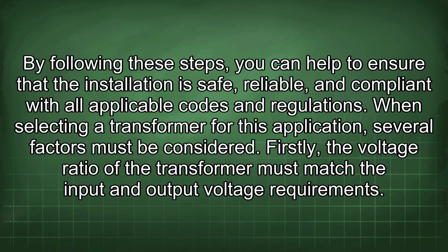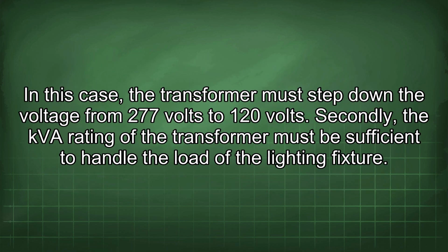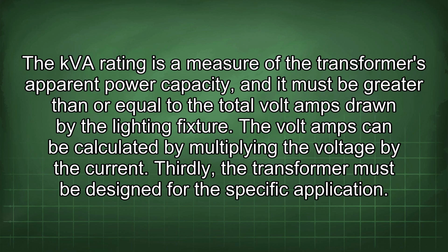When selecting a transformer for this application, several factors must be considered. Firstly, the voltage ratio of the transformer must match the input and output voltage requirements. In this case, the transformer must step down the voltage from 277 volts to 120 volts. Secondly, the kVA rating of the transformer must be sufficient to handle the load of the lighting fixture. The kVA rating is a measure of the transformer's apparent power capacity, and it must be greater than or equal to the total volt-amps drawn by the lighting fixture. The volt-amps can be calculated by multiplying the voltage by the current.